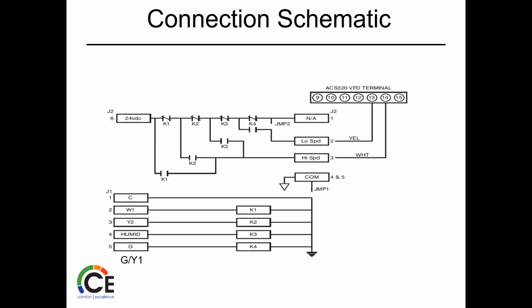And here's that connection. So Y1 and G, we get the same input. We're going to get that K4 to open. Sorry. And we're going to get a number 2 or a yellow input to the terminal, and we're going to get a low speed fan at that point. If we have a Y2 call at that point, or if we get a heating call, then you're going to get high speed fan. And you can test these right at the terminal. We could send that signal there and see if it works. But again, without that keypad, it really doesn't matter because you don't know if it's truly running low or high, because you can't see what it's set up for.